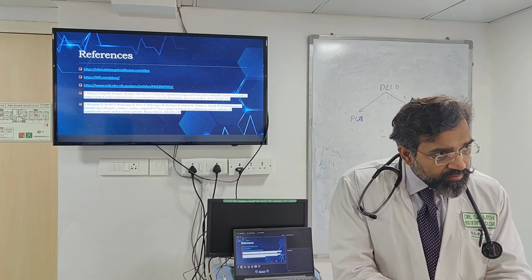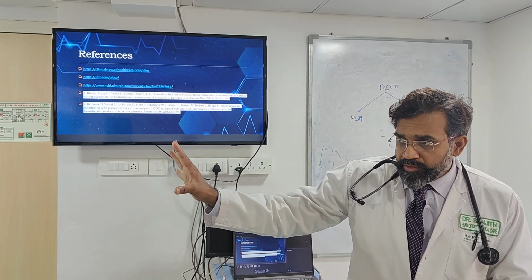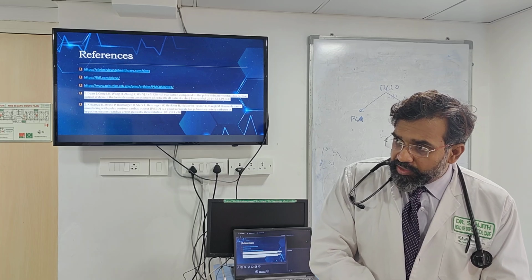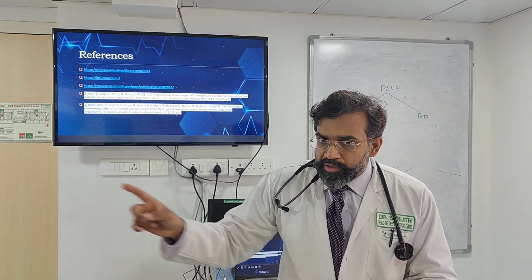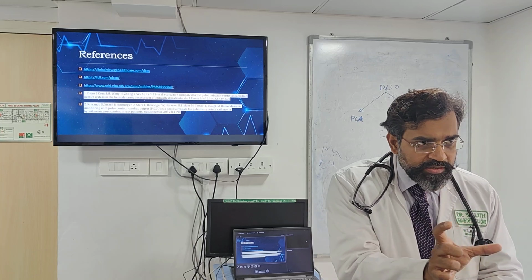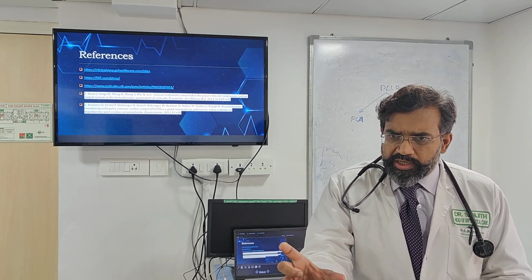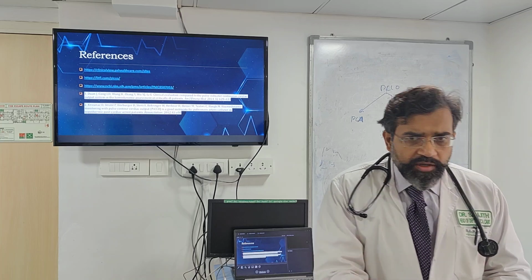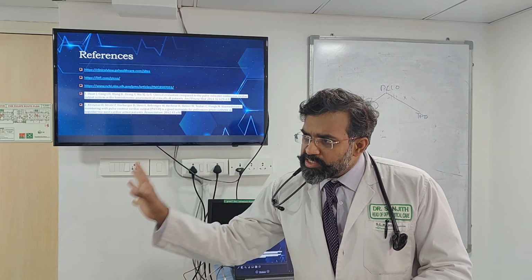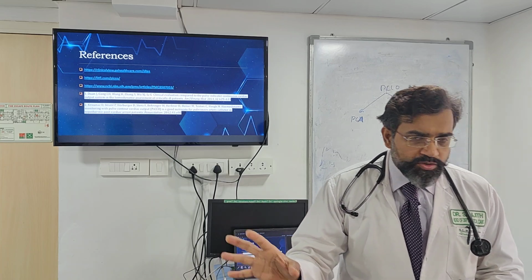You put in a small device, a small transducer, which has software in the machine, and with that it will give you the cardiac output, just this much. You just put one small device onto the radial or femoral arterial line.